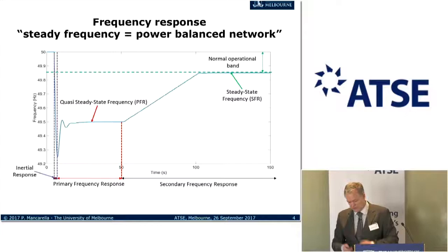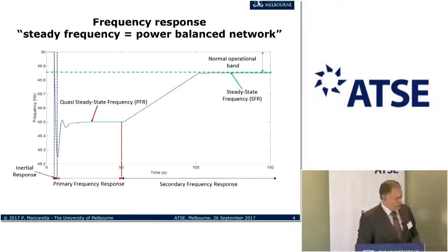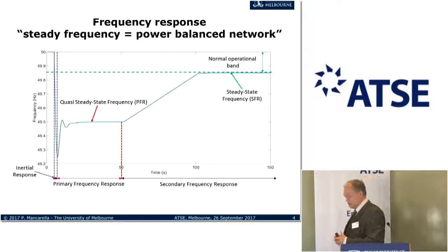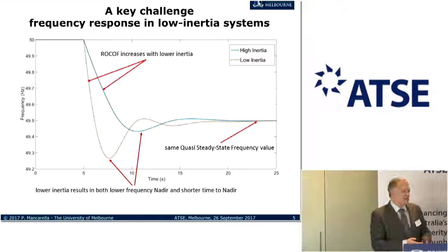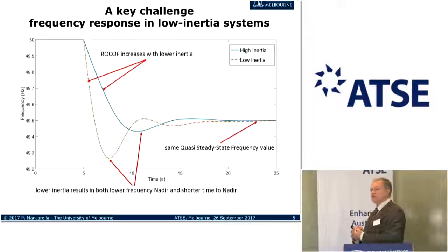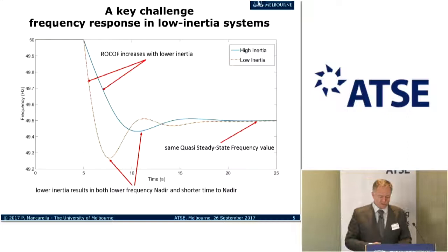In a low inertia system, this picture changes relatively dramatically. Two things happen: the amount of energy we lose per second, or the amount of hertz frequency we lose in the initial phase, is going to be much faster. There's actually less kinetic energy to give up, therefore we lose frequency more quickly. That means our grid is getting more and more unhappy, more quickly.